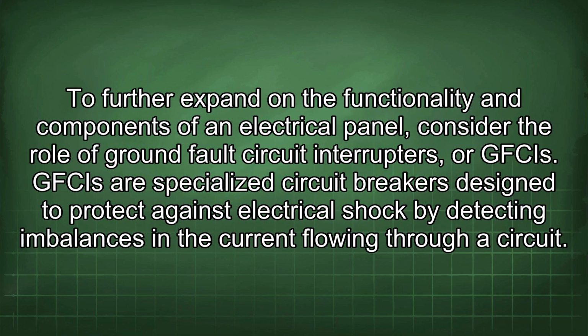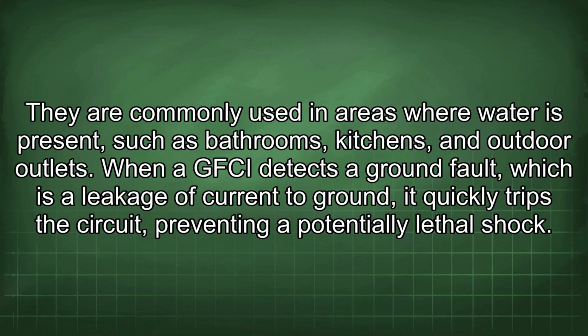To further expand on the functionality and components of an electrical panel, consider the role of ground fault circuit interrupters, or GFCIs. GFCIs are specialized circuit breakers designed to protect against electrical shock by detecting imbalances in the current flowing through a circuit. They are commonly used in areas where water is present, such as bathrooms, kitchens, and outdoor outlets. When a GFCI detects a ground fault, which is a leakage of current to ground, it quickly trips the circuit, preventing a potentially lethal shock.